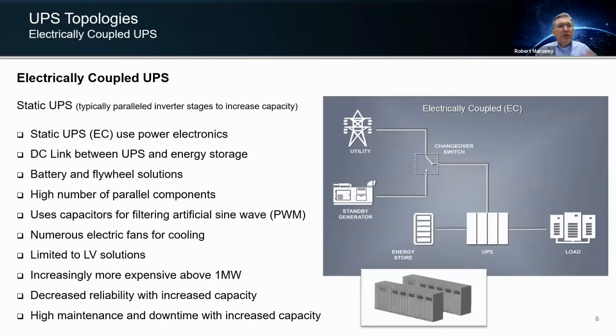Then you see the more traditional electrically connected, or what we call static UPS, which is what we see from a lot of the competitors in the United States using power electronics. The energy storage is connected through a DC bus, okay, and you can have a multitude of energy storage in this kind of application. It can be chemical, batteries, lithium-ion, VRLA, flooded, or it can be kinetic energy or mechanical storage like a flywheel.